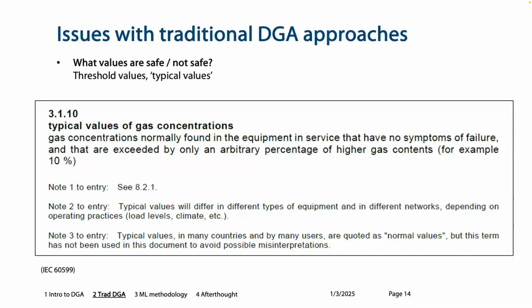So the typical value doesn't really say a safe value, because that's a disclaimer, okay? It's just typical, it's not a safe value. And the typical value is the gas concentration normally found that have no symptoms of failure and that are exceeded by an arbitrary percentage of higher gas contents. What do you mean by that? So what it says is that if the top 10% of your fleet of transformers has this value, then you can decide an arbitrary percentage above that. And by those values, you will decide as unhealthy. That's what it tries to say essentially.